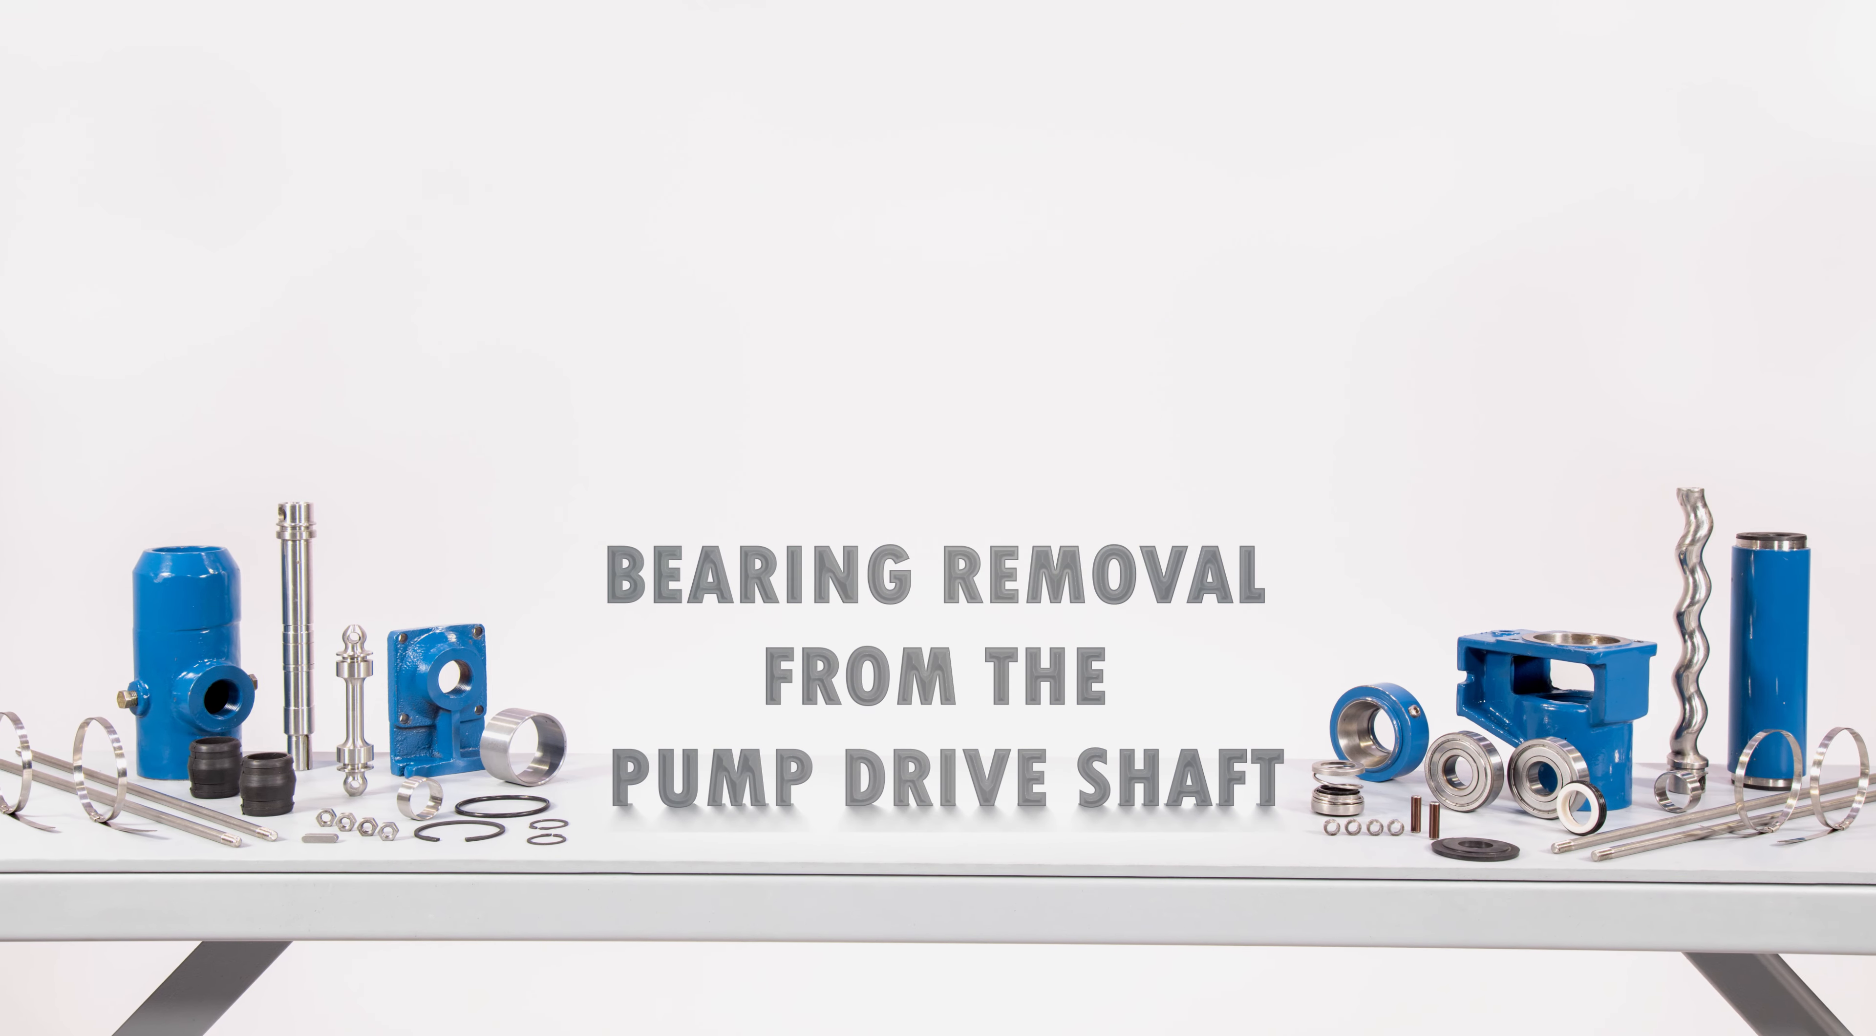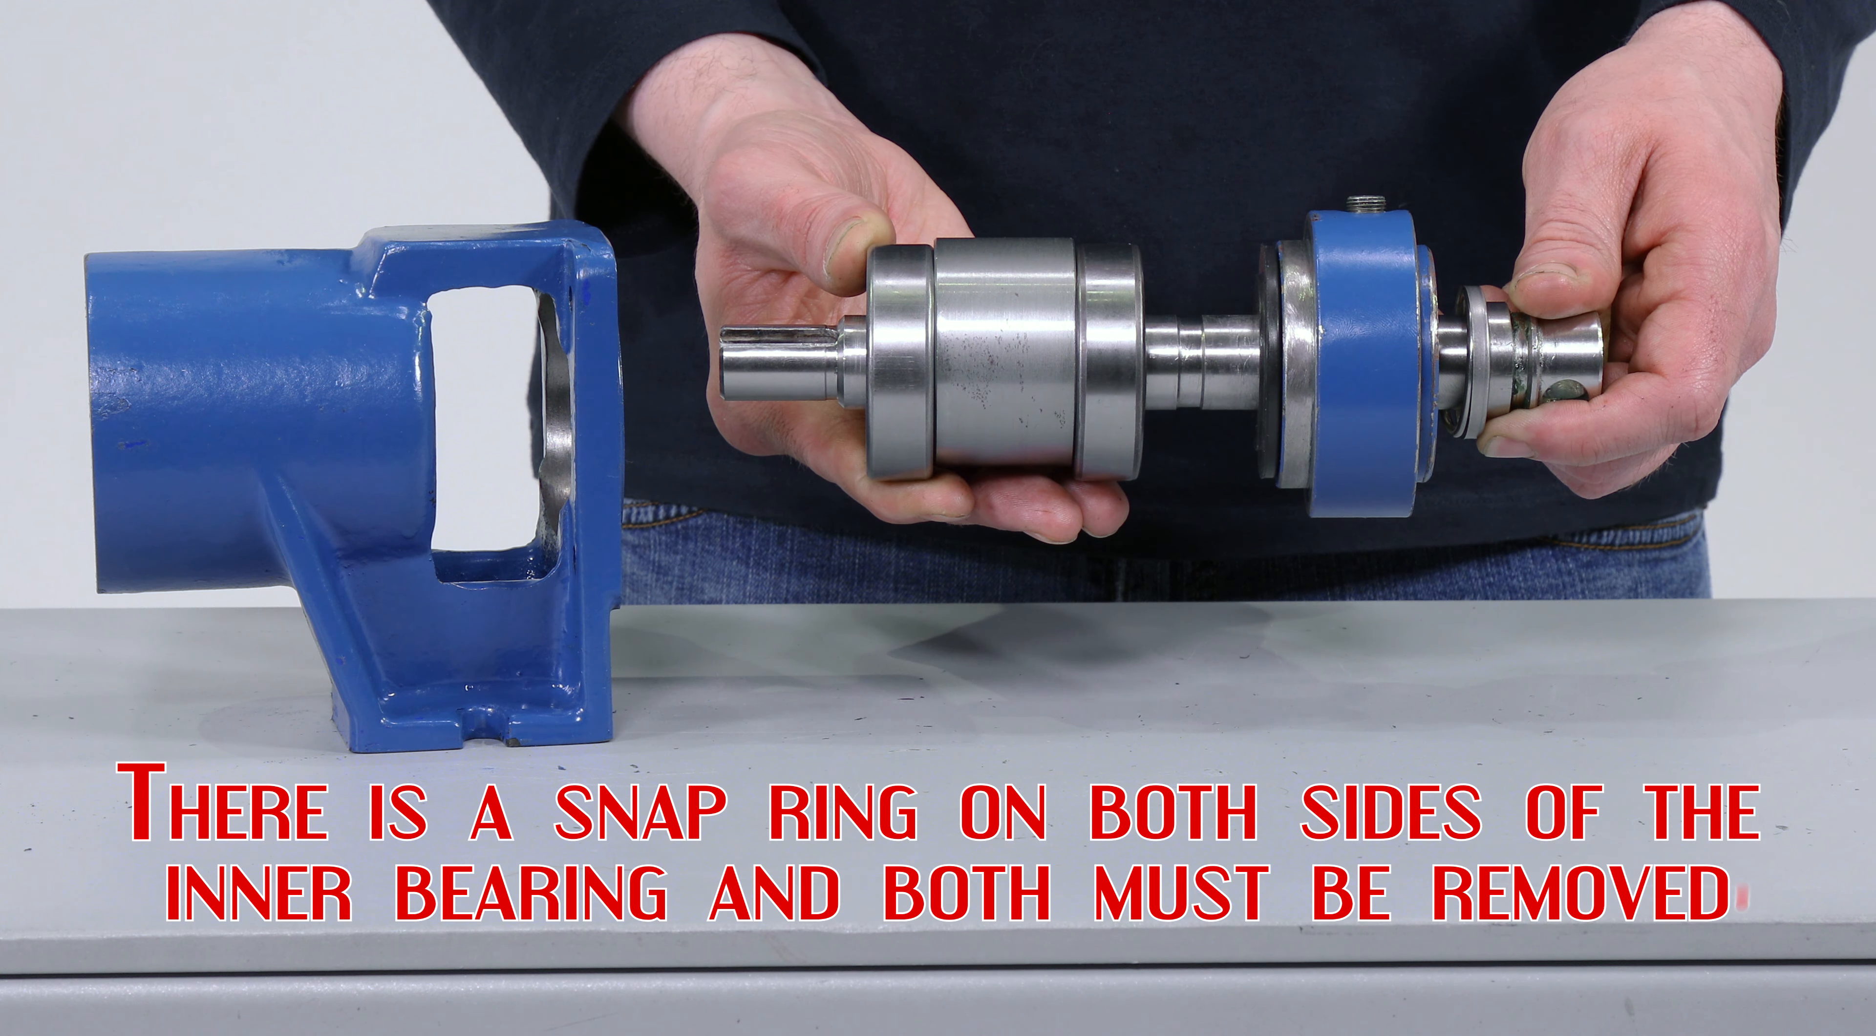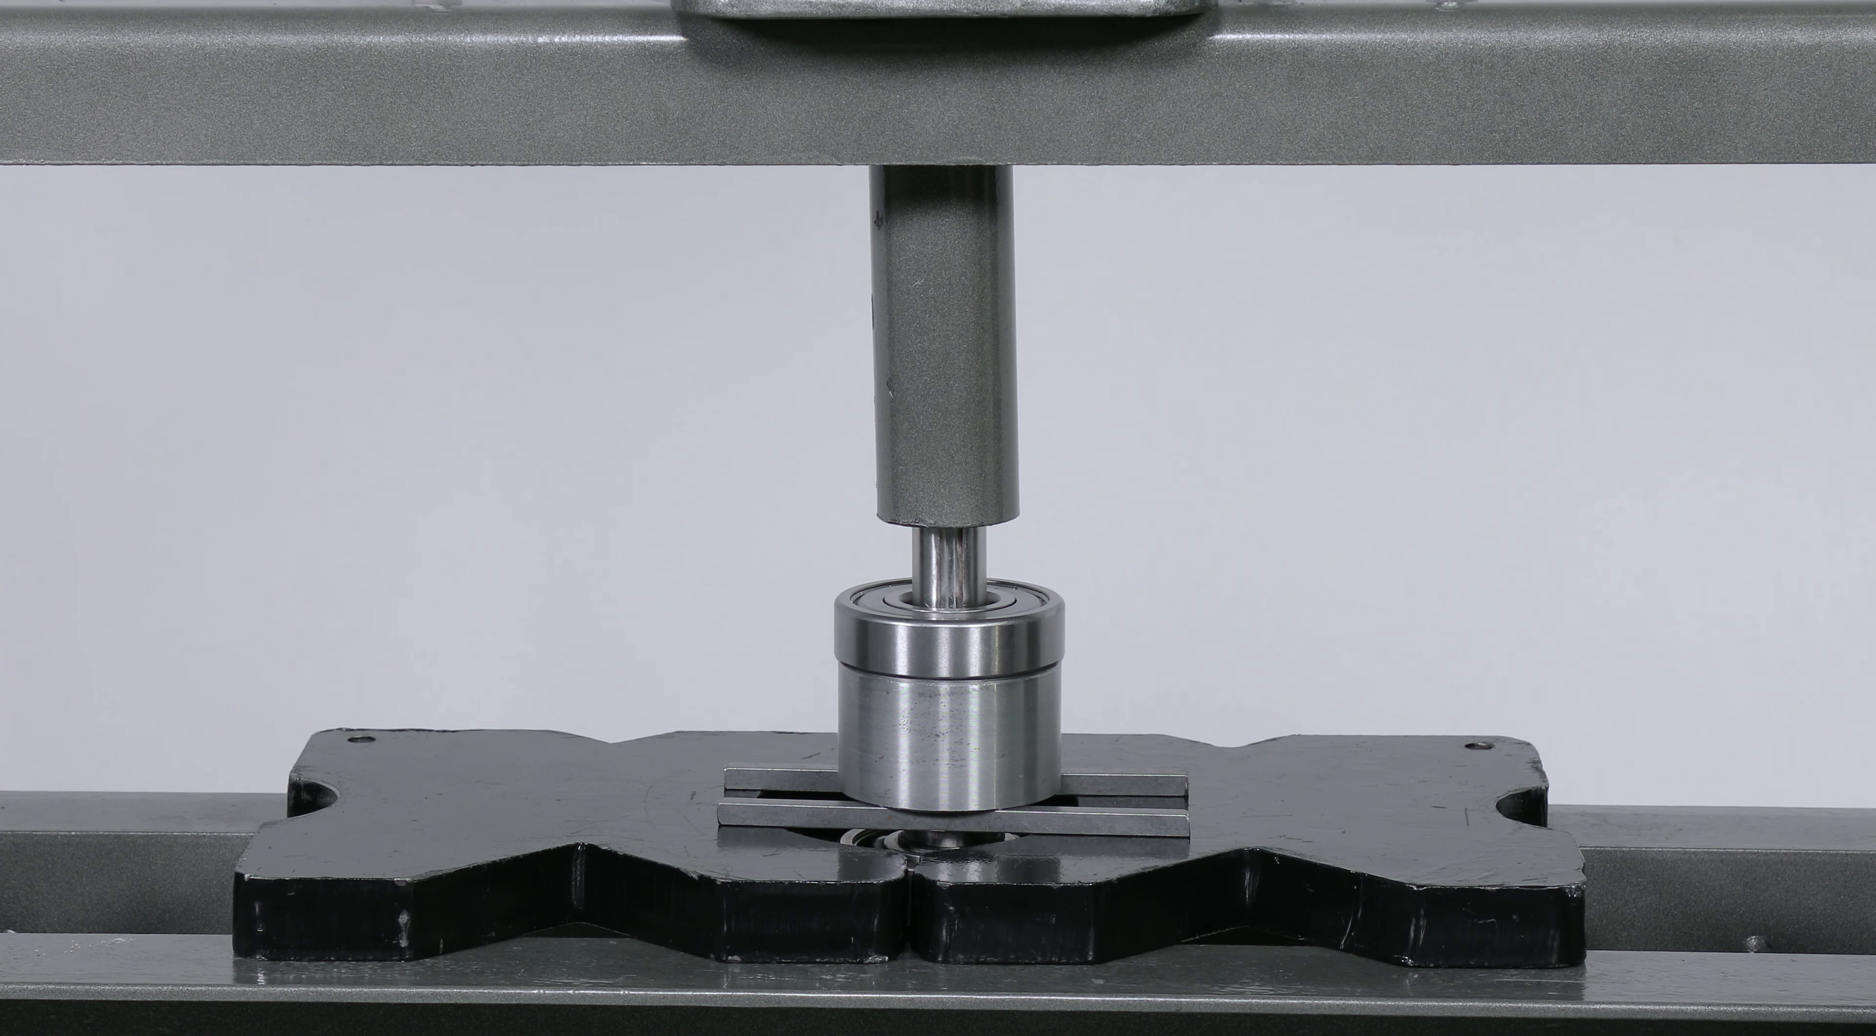Bearing removal from the pump drive shaft. There is a snap ring on both sides of the inner bearing and both snap rings must be removed. If using a sealed spacer, tap the spacer side to side until you have enough room to place the drive shaft in a press and remove the spacer and bearing.